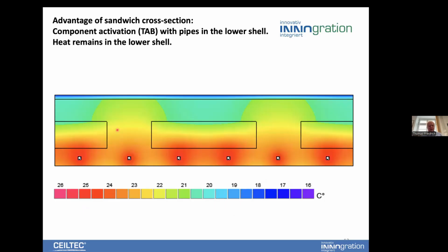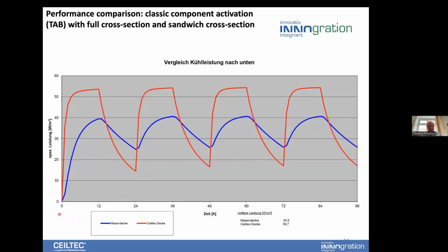Coming back to our sandwich cross section, when you have the tubes in here, the heat which is transferred by the tubes to the concrete remains in the lower part, and that is exactly what we need to bring it to the surface. It is not just a point of storage - I will come back to that - but also a point of comfort, and with this system we achieve that comfort. As you can see here, the difference between the sandwich cross-section element, the red line, and the blue line, which is the fully flat slab cross-section.